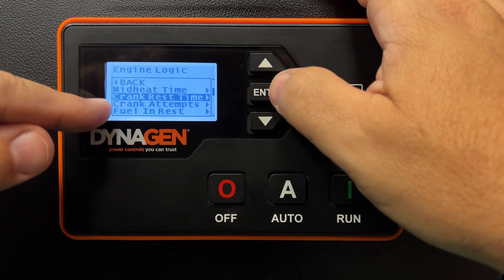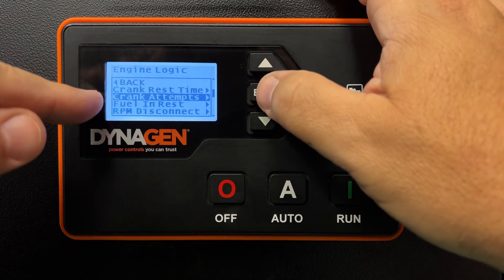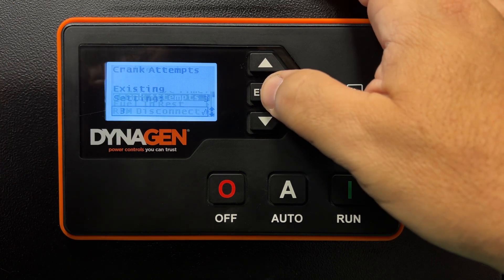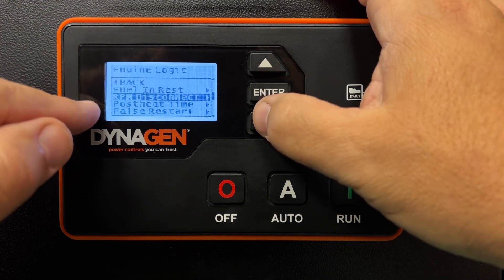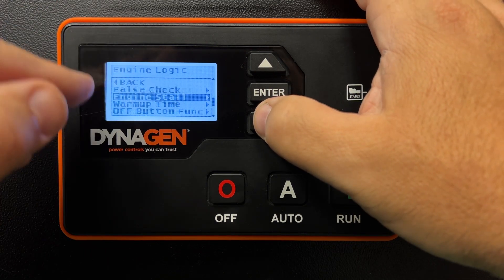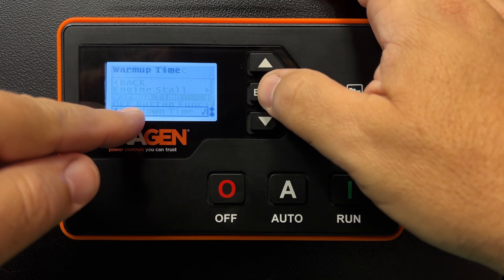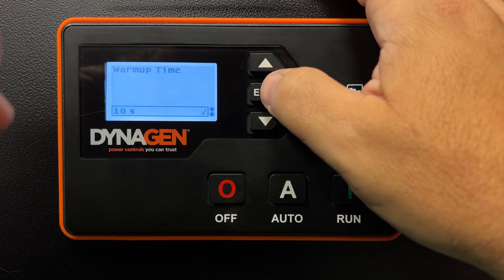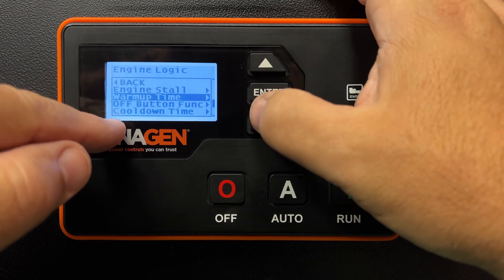There's a Crank Rest Time — it tells the controller how long to wait before trying again and how many times to try cranking. We normally have it set for three attempts. Fuel In Rest — don't touch that. RPM disconnect — don't touch that. There are a bunch of other settings; if you don't know what you're doing, don't go in there. Warm-up time is not what you think — 10 seconds is telling it to ignore sensors during the warm-up period. You don't want to adjust those settings.